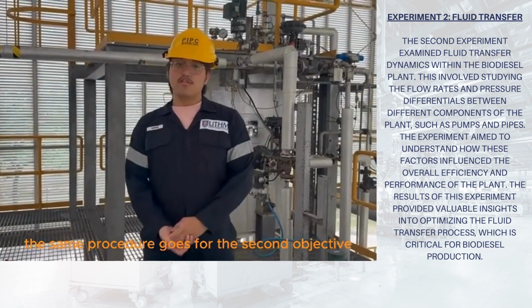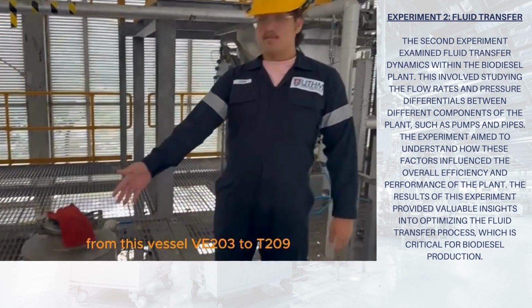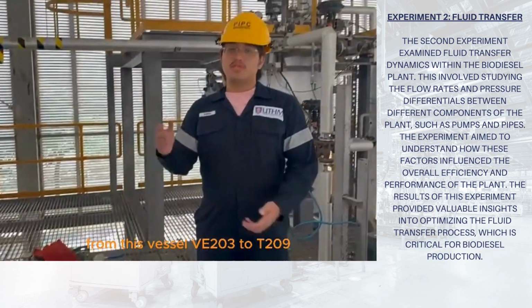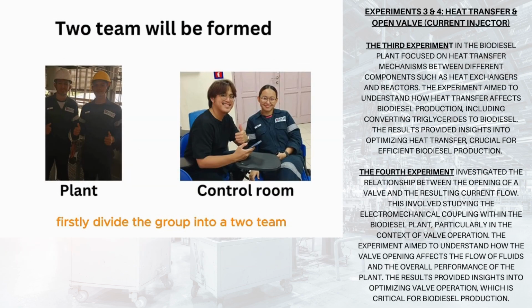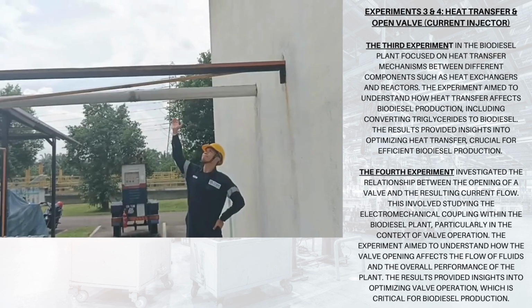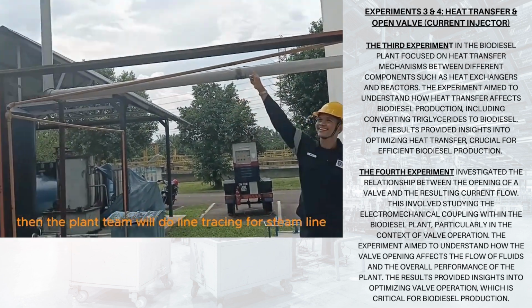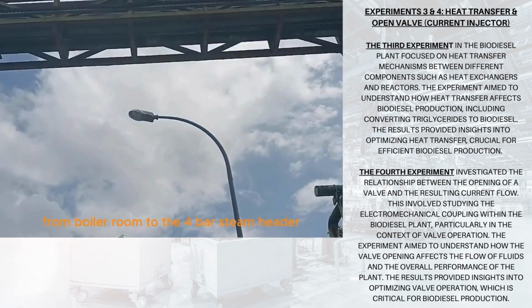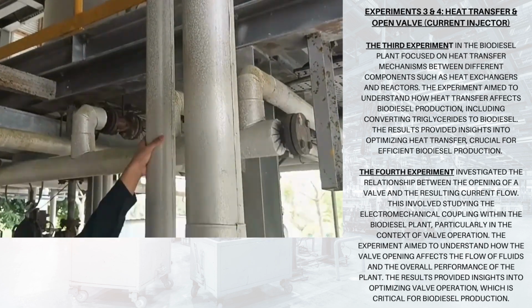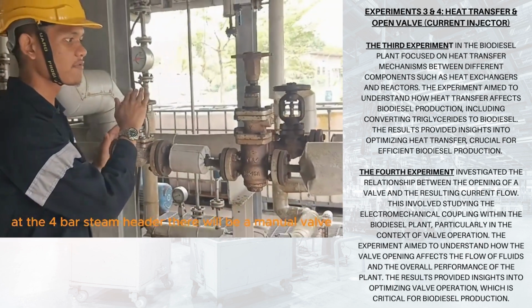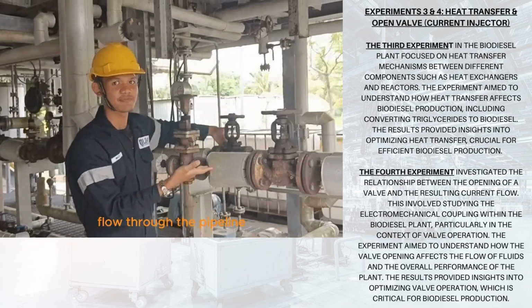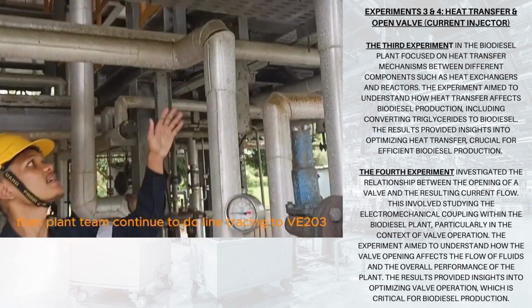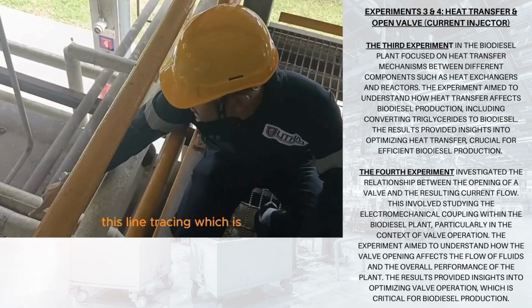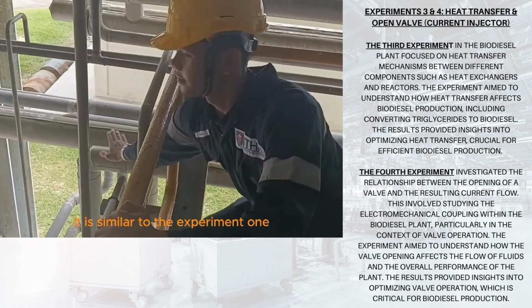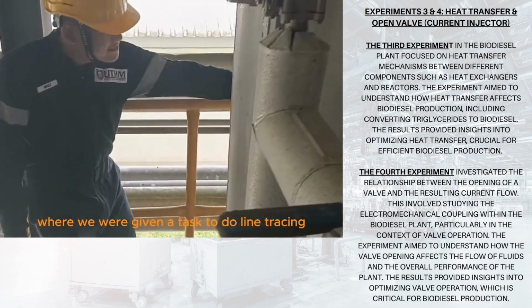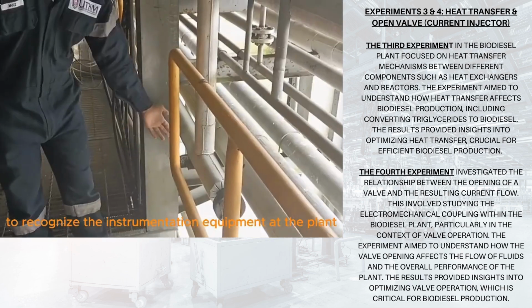And then the same procedure goes for the second objective, which is from this vessel, VE203, to T209. Firstly, divide the group into two teams, one at the plant and another at the control room. Then, the plant team will do line tracing for the steam line from the boiler room to the 4-bar steam header. At the 4-bar steam header, there is a manual valve that needs to be opened to allow the steam to flow through the pipeline. Then, the plant team continues line tracing to VE203. This line tracing is similar to experiment 1, where we were given a task to do line tracing to recognize the instrumentation equipment at the biodiesel plant.